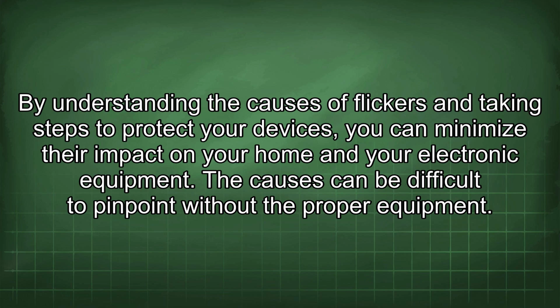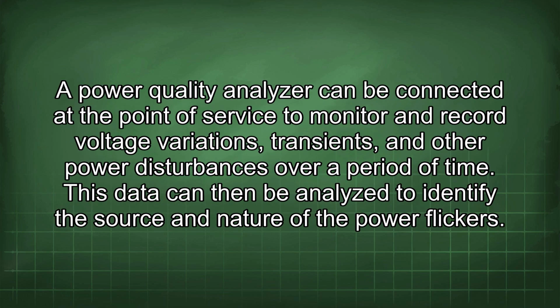The causes can be difficult to pinpoint without the proper equipment. A power quality analyzer could be connected at the point of service to monitor and record voltage variations, transients, and other power disturbances over a period of time. This data can then be analyzed to identify the source and nature of the power flickers.